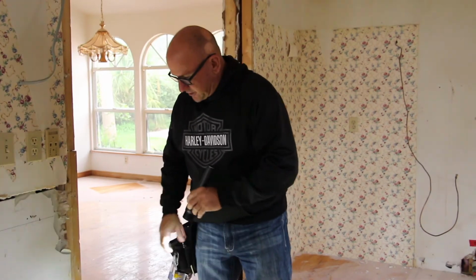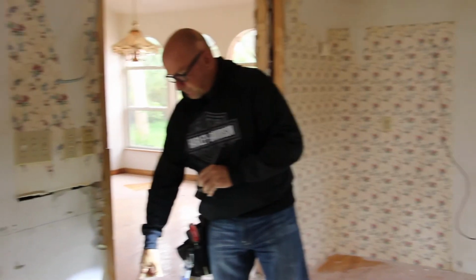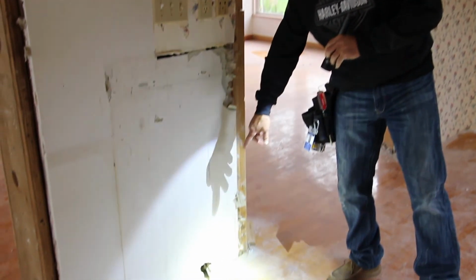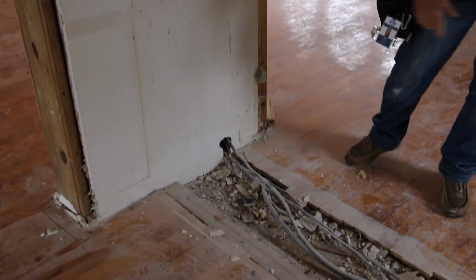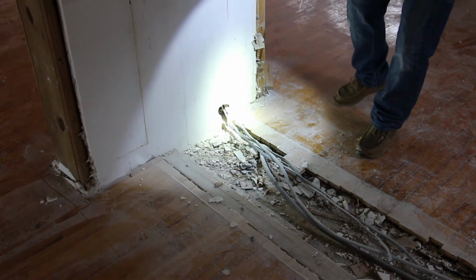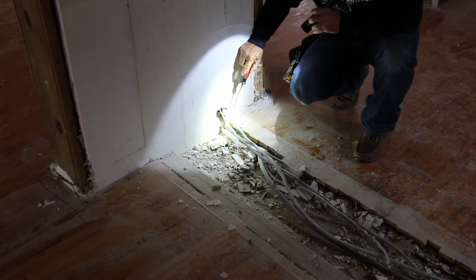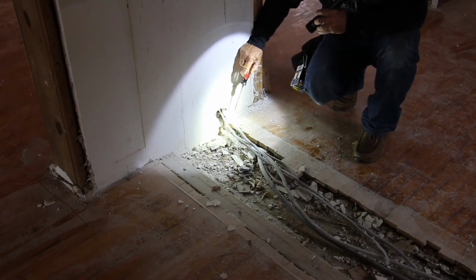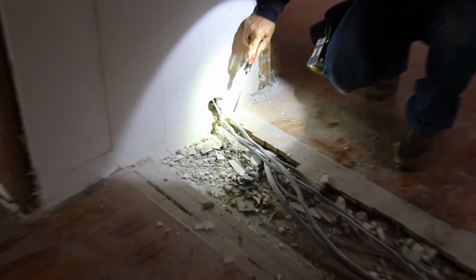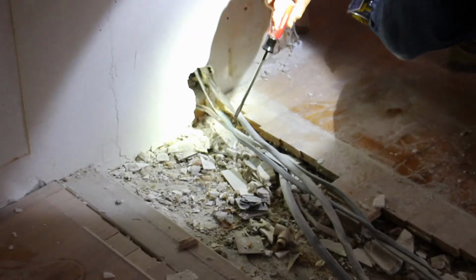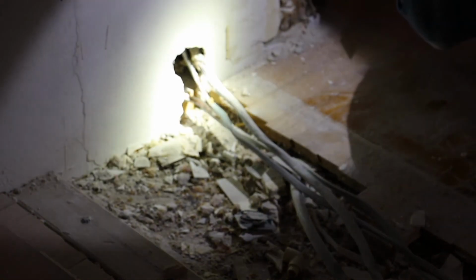One of the things we see right here on the bottom of this, where these feeders come out of the wall and were run through the cabinets, is that all of these conductors are now exposed. This is a very dangerous arc fault condition. It could cause a fire, and all of this wiring will need to be replaced from here all the way back to at least a junction box or panel location in order to make this safe.